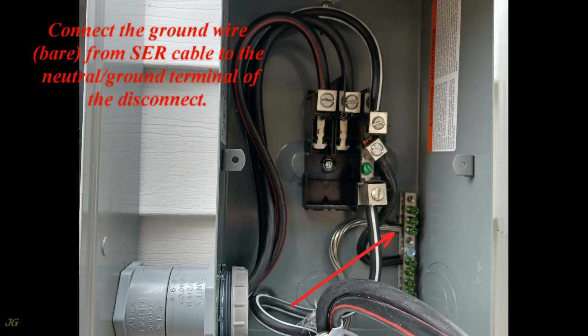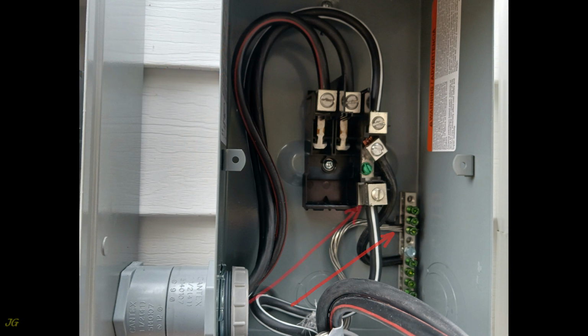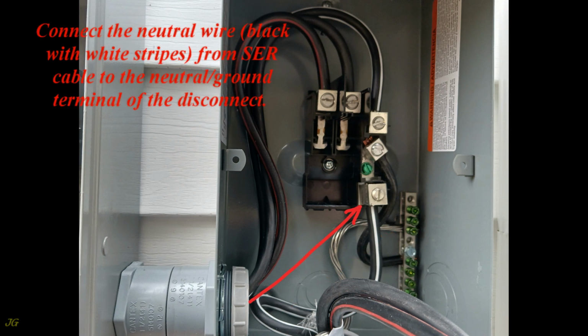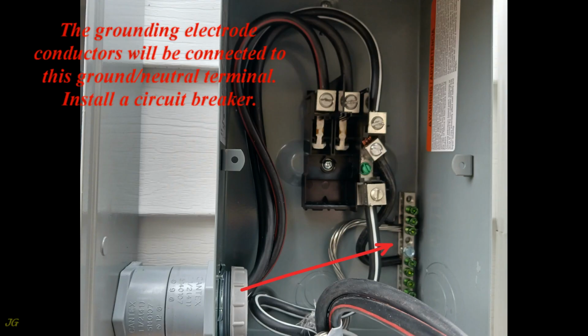Connect the ground wire, bare, from SER cable to the neutral, ground terminal of the disconnect. Connect the neutral wire, black with white stripes, from SER cable to the neutral, ground terminal of the disconnect. The grounding electrode conductors will be connected to this ground neutral terminal.